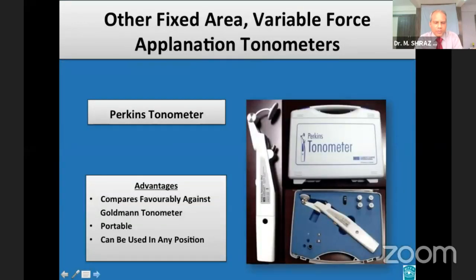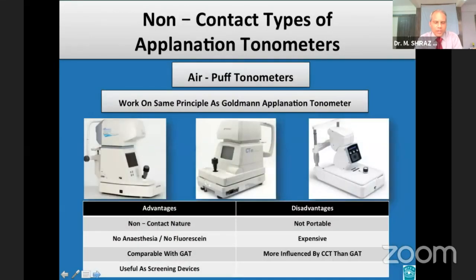The Perkins tonometer uses the same principle as GAT but is portable and can be used in any position. The commonly used non-contact tonometer is an applanation tonometer which uses a column of air to flatten the non-anesthetized cornea. The advantages of the NCT include its non-contact nature and it does not require topical anesthesia or instillation of fluorescein dye.